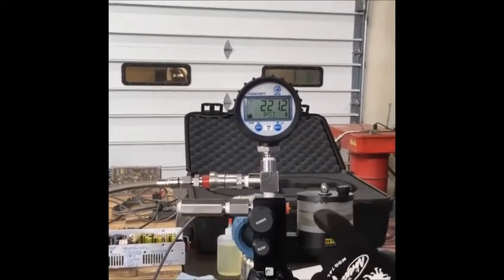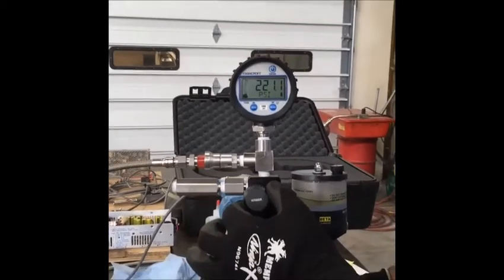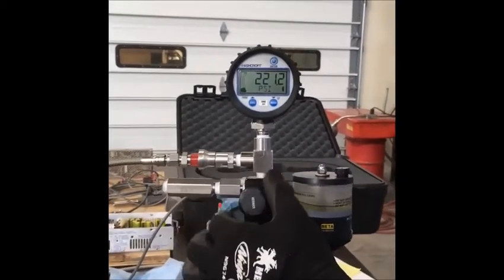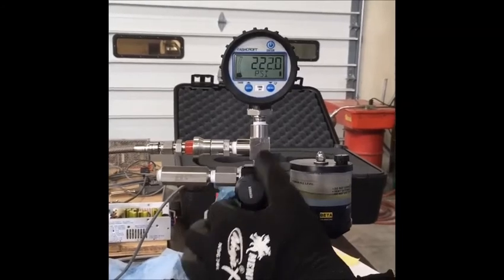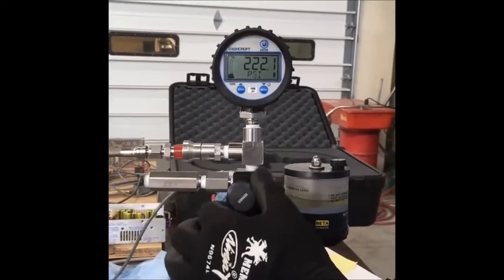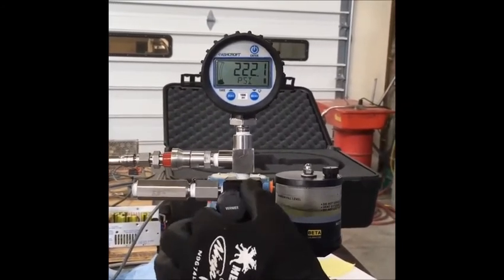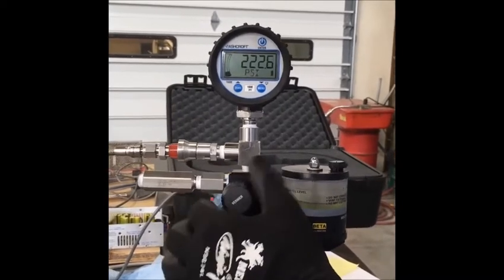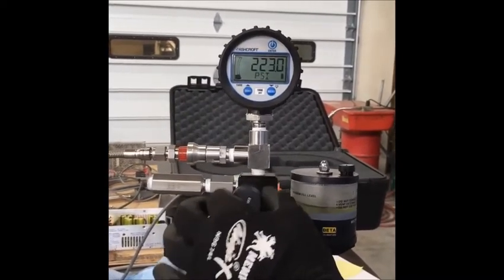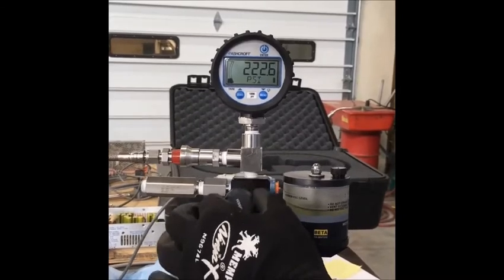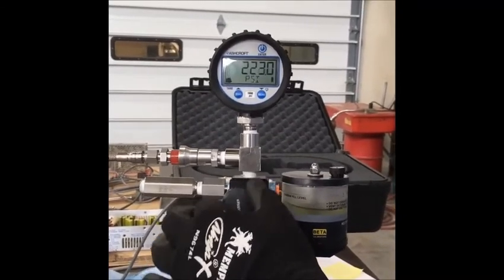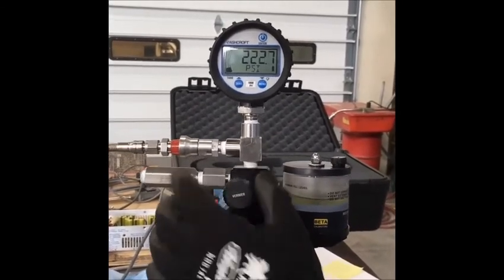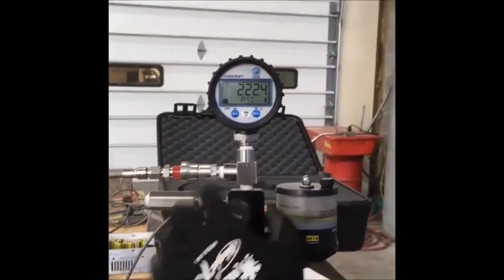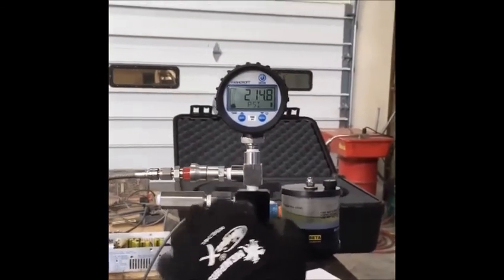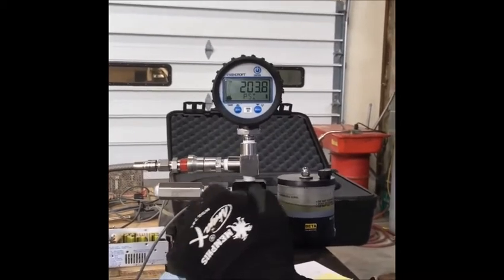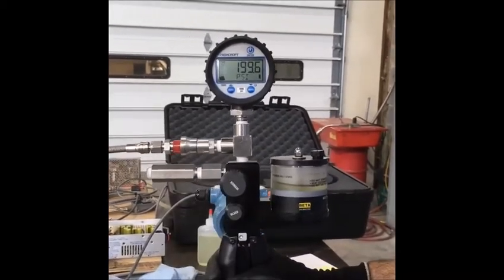Once you're close to the cutout pressure, you can use the vernier dial on the pump to raise the pressure a little more. It just takes some dead volume out of the pump. So I can raise it maybe 3 or 4 psi is about all, and it'll come up slowly so you can approach your high pressure cutout on the system. Now I just ran out of travel here, which means I'll have to back this one off and I'll have to give it another little pump. Alright, so back the vernier off, I'll give it a little bit more.